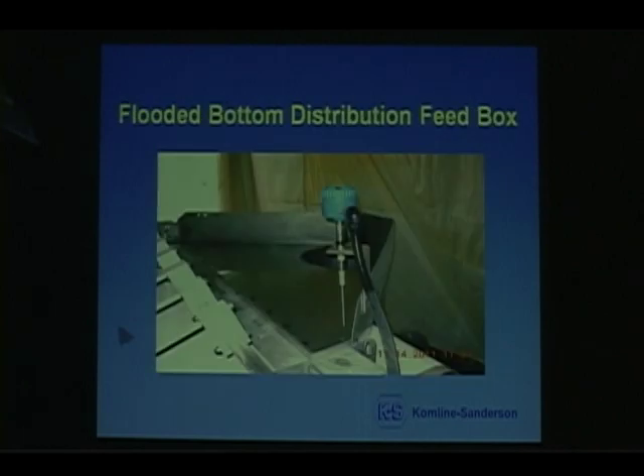The flooded bottom distribution feed box is what you're looking at. The blue probe, the Drexelbrook probe, is a high sludge level probe. If the sludge should rise up and touch the probe, it will shut the sludge and polymer off, preventing the sludge from overflowing on the press.